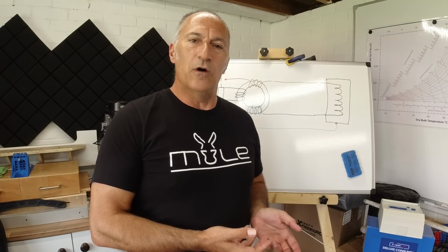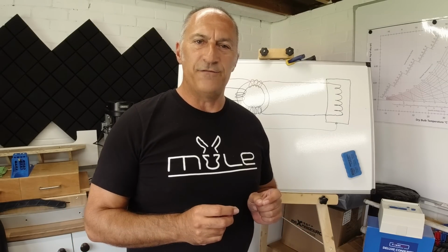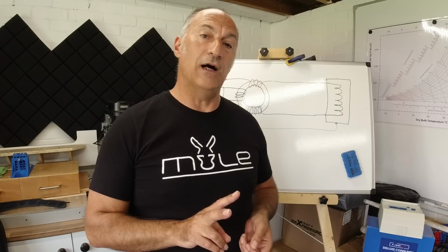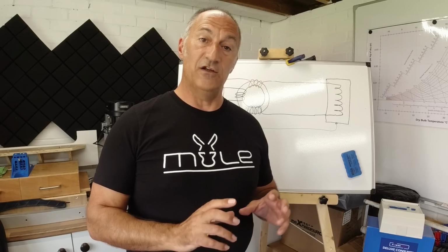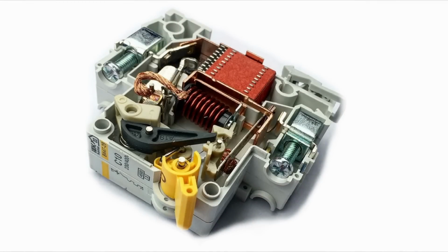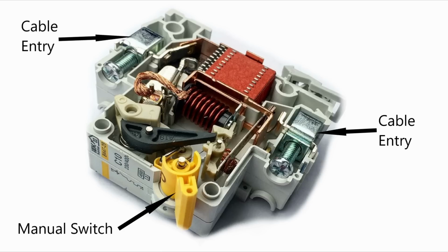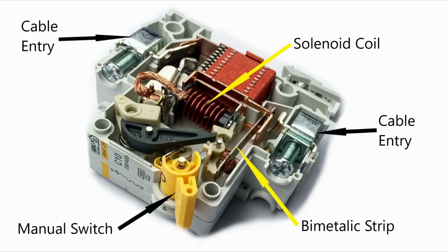So how does the MCB work, and how does it differ from a normal wired fuse? Well, it actually works in two different ways. And we'll jump onto the computer, have a look at the internal workings of the MCB, and I'll explain how it works. So here we've taken the side cover off a miniature circuit breaker so you can see the internal workings. And there's a couple of key parts that we need to look at. You have the switch on the front of the device, which you can manually turn the circuit on and off. You have screw terminals top and bottom for the cable entry. But the two active items within the MCB that cause it to trip automatically are first this bimetallic strip, and secondly this little solenoid coil in the middle.